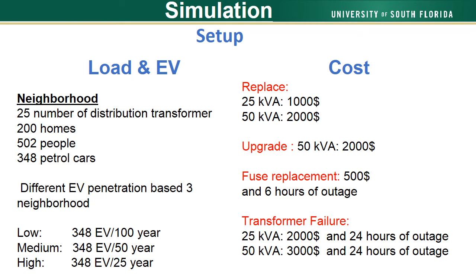The scheduled replacement by a 25 kVA transformer costs $1,000, whereas $2,000 for upgradation to a 50 kVA. Transformer failure causes 24 hours of outage and replacement cost, $2,000 for replacement by 25 kVA or $3,000 for replacement by 50 kVA. A fuse blow costs $500 and 6 hours of outage. Failure and fuse related costs are higher as they require emergency service and get no salvage value for the failed transformer. Furthermore, they cause unexpected outages that cost the utility in terms of unserved electricity and customer dissatisfaction.